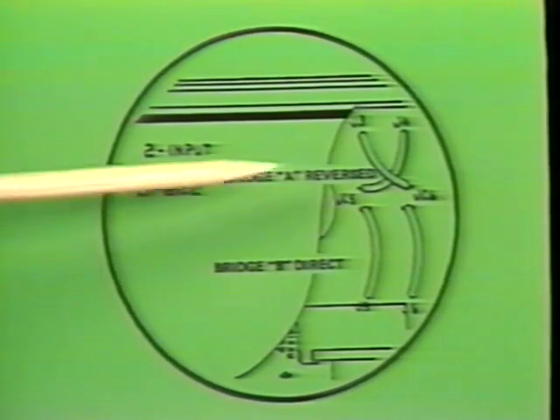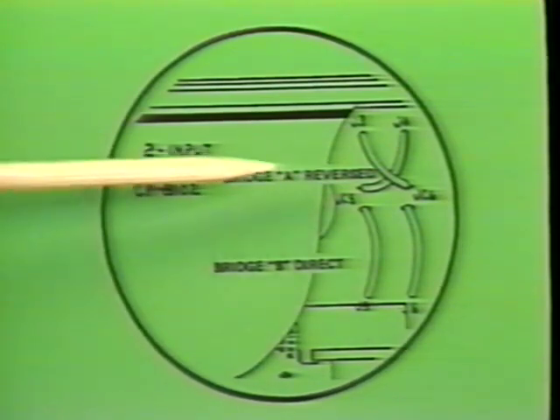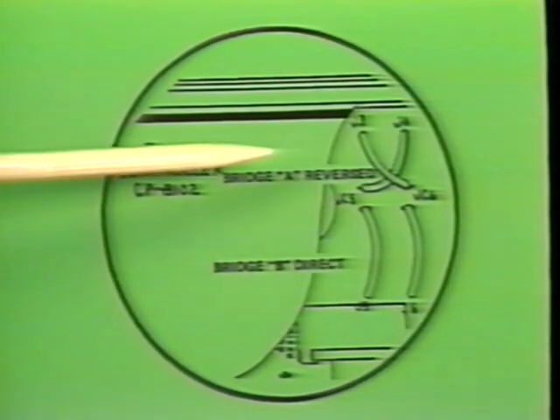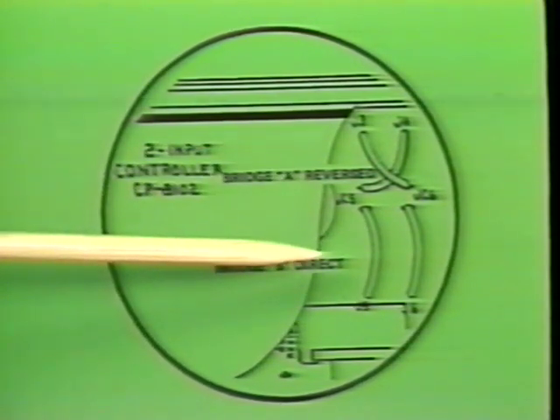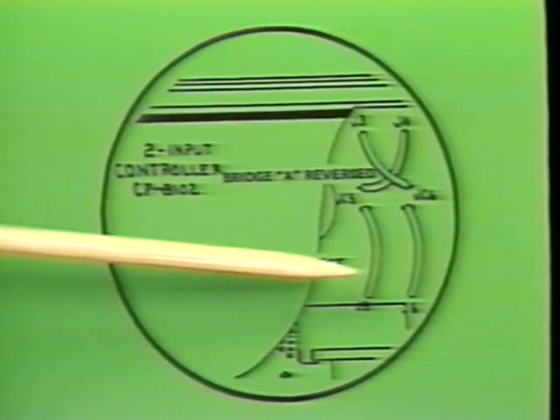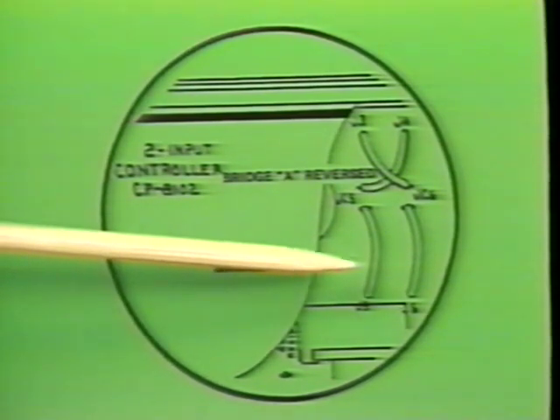This diagram shows a change. Now the bridge A jumpers are crossed, giving us reverse action for the controller. Note the bridge B jumpers have not changed. Now the two pairs are not the same. The result, the controller has direct action.